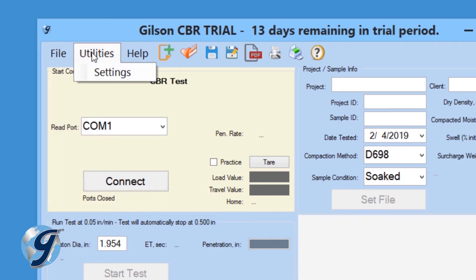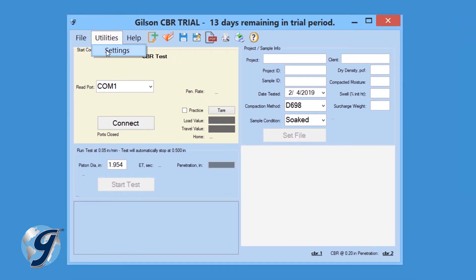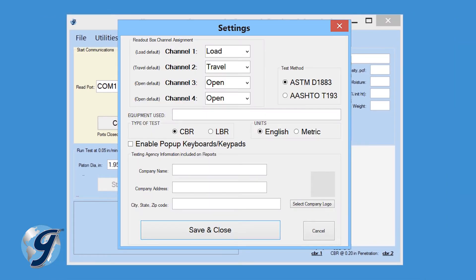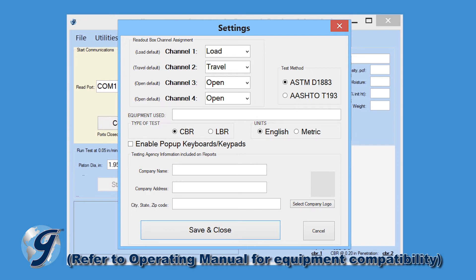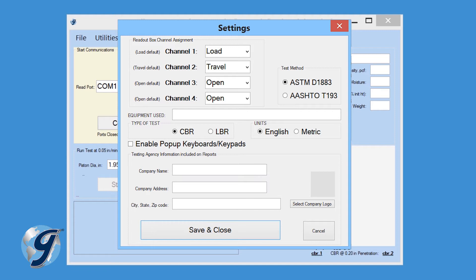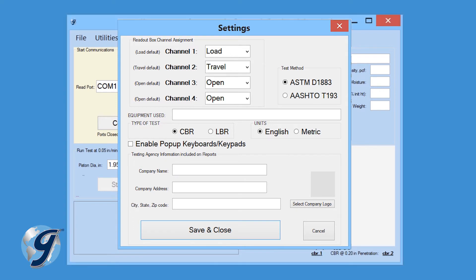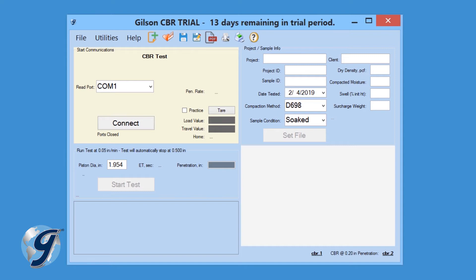Click on Utilities and we can enter the test settings. Click on Settings and a new menu opens. Here we can enter the Readout box channel assignment, enter the equipment used to perform the test, choose the type of test, enable or disable the pop-up keyboard feature, and indicate whether we want the report in metric or imperial units. The user can also enter the testing agency information and logo, which are displayed on the test report. Click Save and Close to save the information to the current test. Click on Help to find assistance with this program, contact information, or to activate your software.